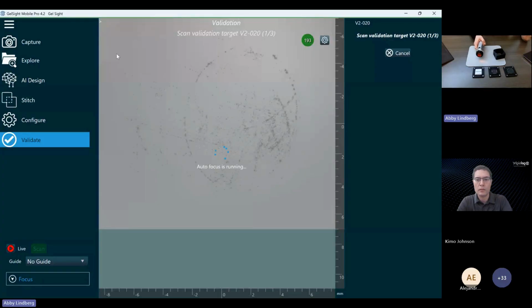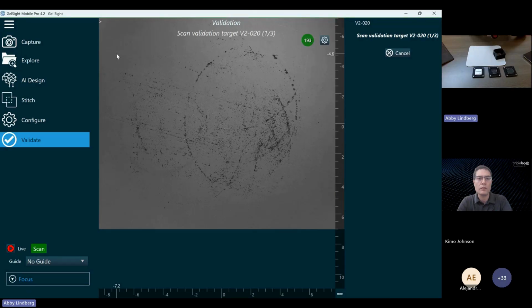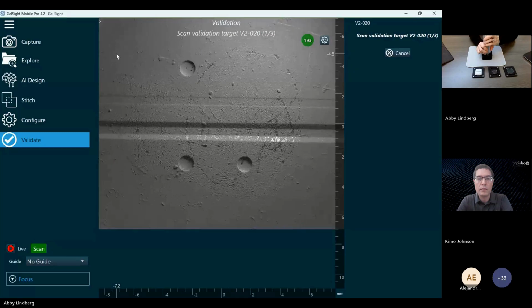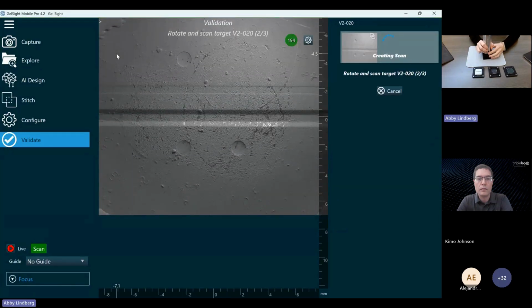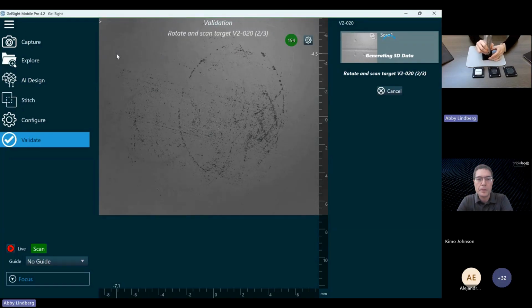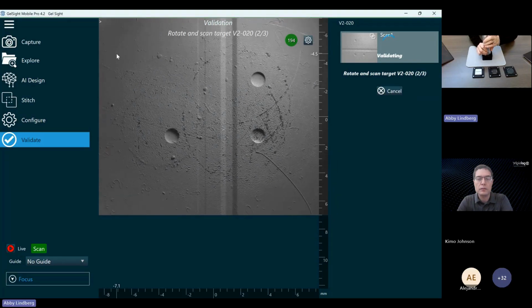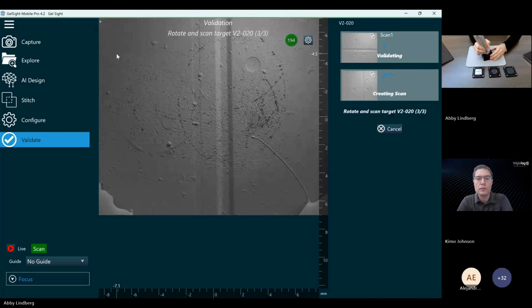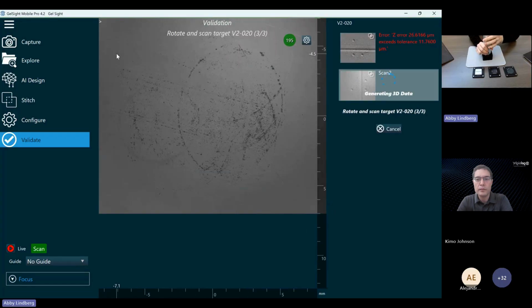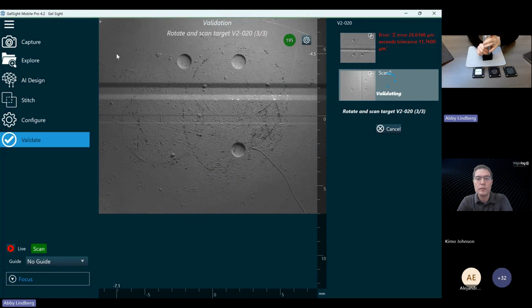The first thing that you'll notice after the system focuses is that this gel doesn't look that great, right? So this is definitely an example of failing validation. And before I take the scans, I'll even hold the system up to the video camera here so that you can see what that damage looks like. You can see all that wear through that pigment layer. And now I'll go ahead and take some scans of the validation plate. So we'll come in here, we'll press down. You can even see how the illumination on that gel changes as it conforms into that groove. We'll go ahead and take the next one. And we'll take the last one here. This gel is also pretty sticky, which you might see when I'm pulling it off of the surface.